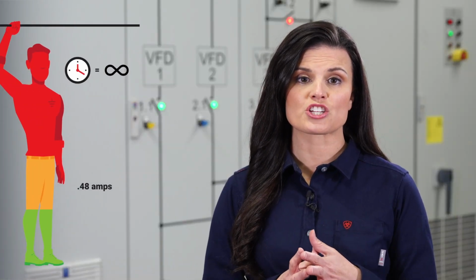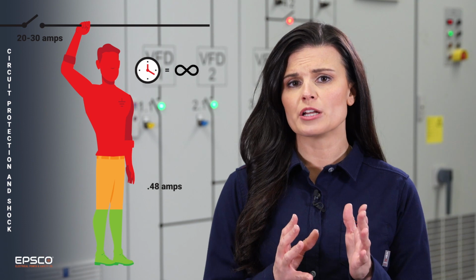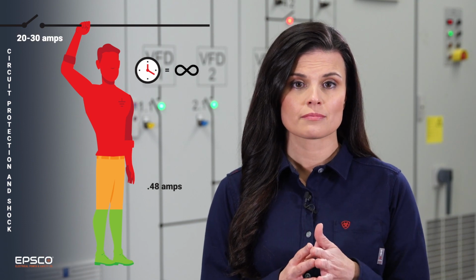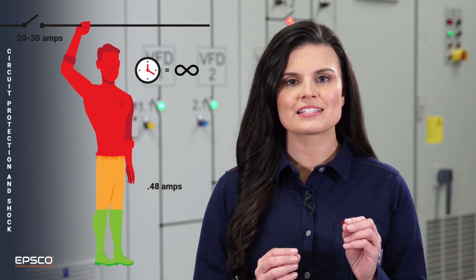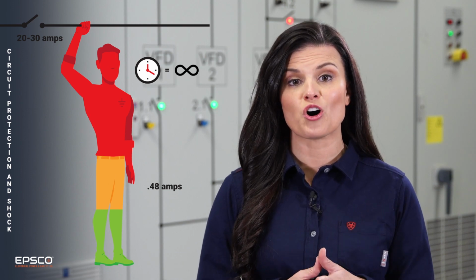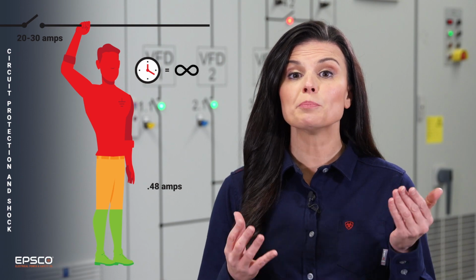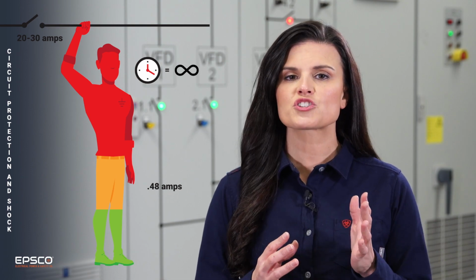We've been using 1,000 ohms of resistance in our example, but again, resistance will decrease rapidly once current breaks the skin. In almost no time, the current will cause your muscles to contract, leaving you locked in the circuit until help arrives. You might be thinking you'll be safe because you have circuit protection, but keep in mind the smallest breaker in most facilities is 20 to 30 amps. In our example, the circuit will never even detect an issue and the device won't interrupt the fault. This is especially true when we have a completed circuit between two phases, or when a circuit isn't designed with adequate ground fault protection.